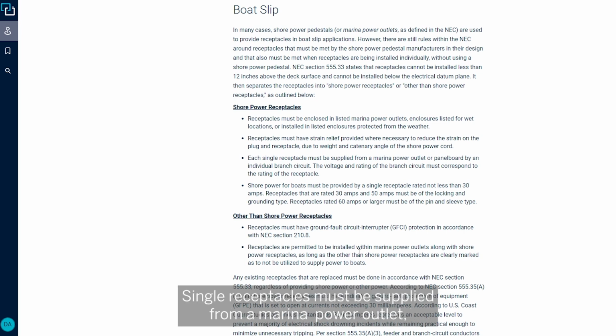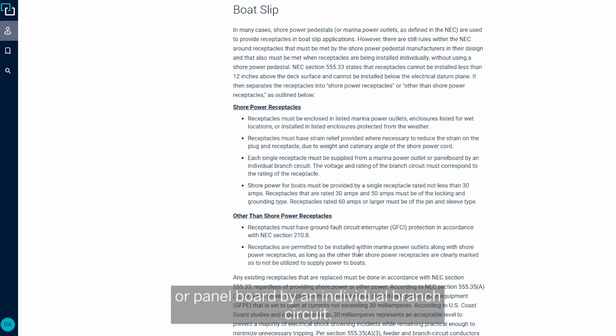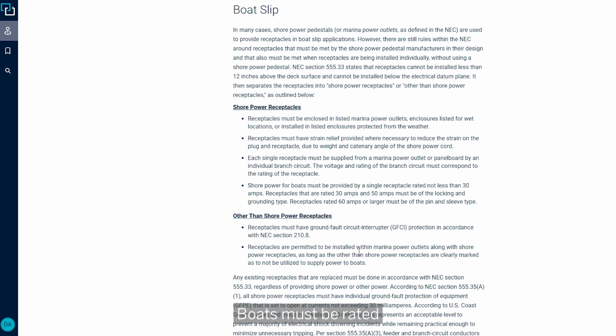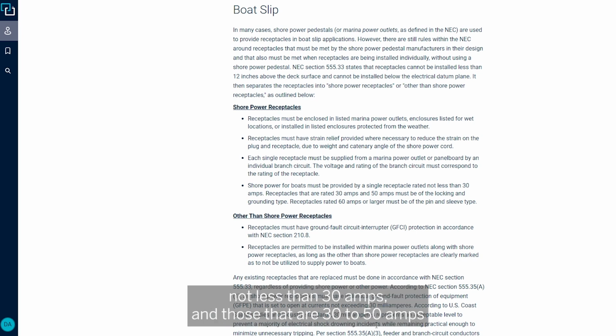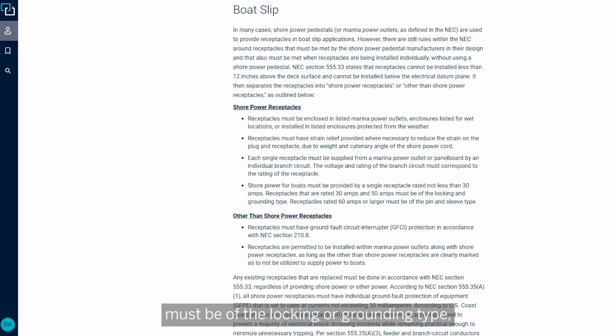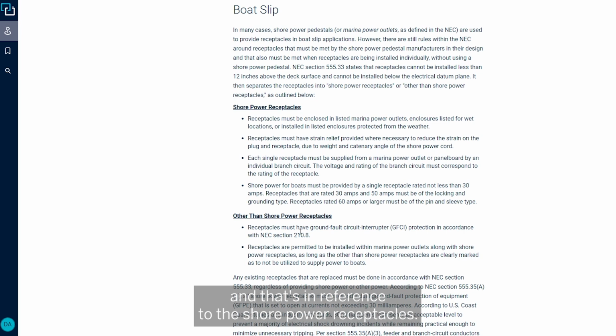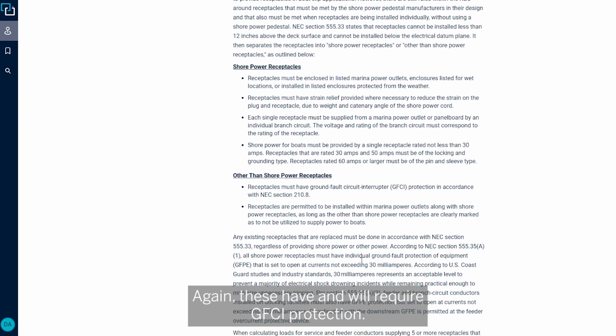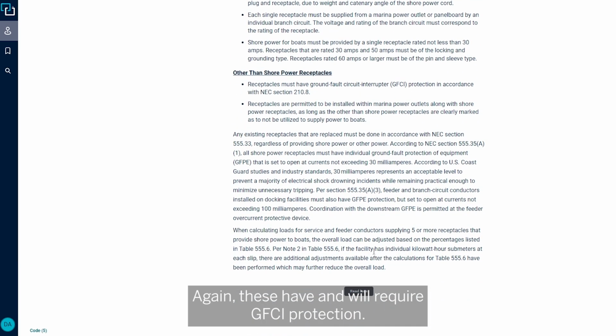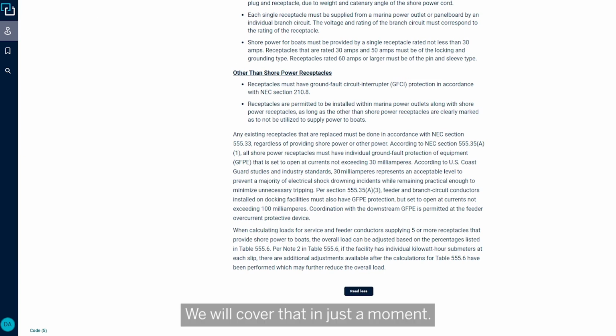Single receptacles must be supplied from a marina power outlet or panel board by an individual branch circuit. Boats must be rated not less than 30 amps, and those that are 30 to 50 amps must be of the locking or grounding type, and that's in reference to the shore power receptacles. So the receptacles that are 30 to 50 must be of the locking type. Receptacles rated 60 amps or larger are typically a pin and sleeve. Again, these will require GFCI protection. We will cover that in just a moment.